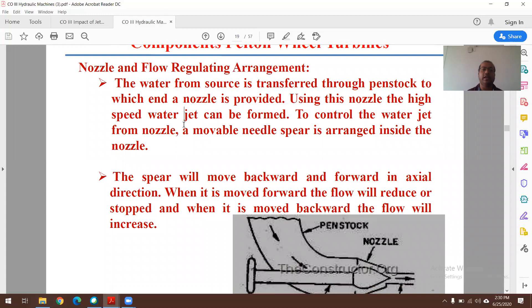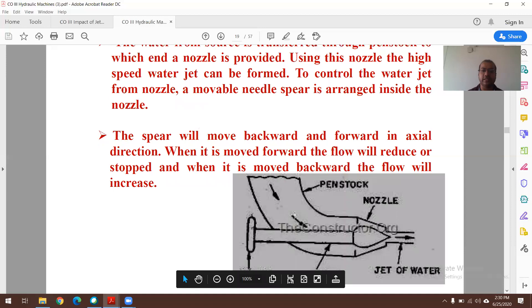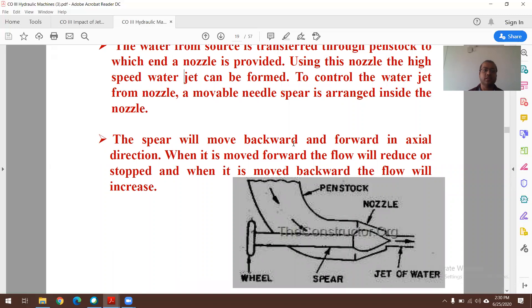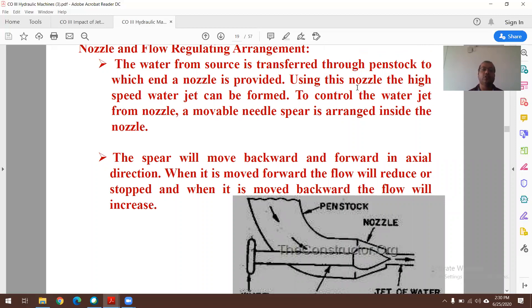The Pelton wheel turbine consists of a nozzle and flow-regulating arrangement. Water from the source is transferred through the penstock, and a nozzle at the end forms a high-speed water jet. To control the water jet, a movable needle spear is arranged inside the nozzle to regulate the flow. When the spear moves forward, the flow reduces due to obstruction in the passage. When it moves backward, the flow increases.